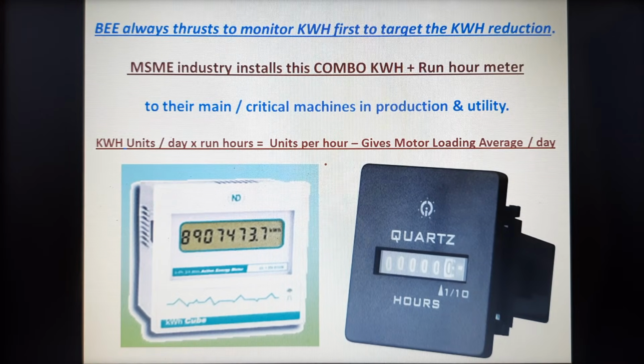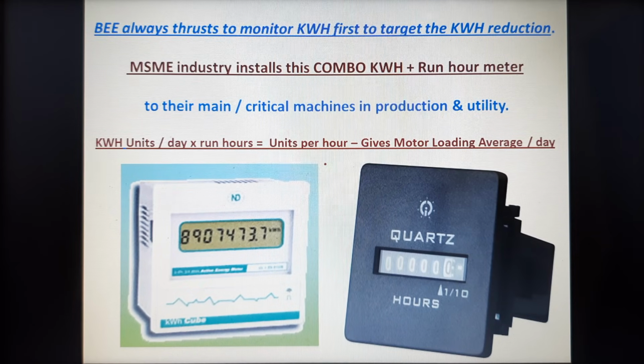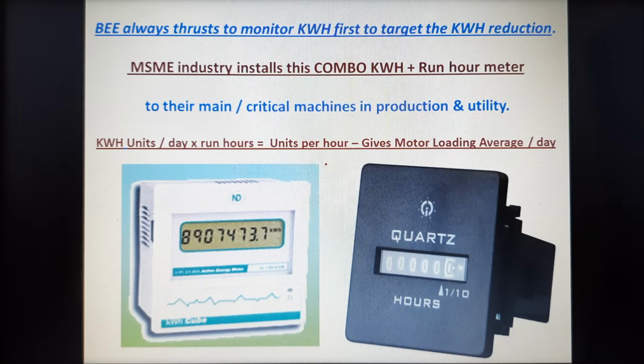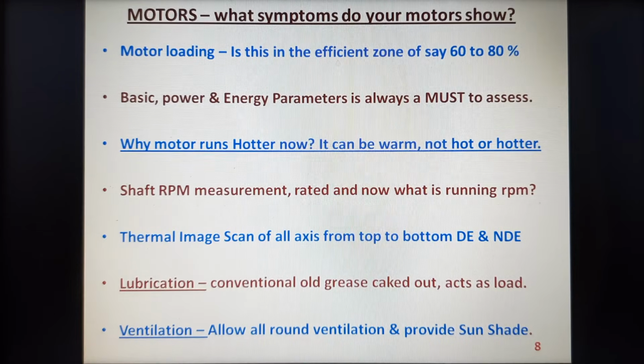This is what I am just talking about: combo meters of kWh and run hour meter to be installed on each and every pump, utility, compressor or blower, and on the production machines also. You know the kWh units consumed per day, and dividing by the run hours will definitely give the average units per hour consumed per day. You know the motor average loading. This will give an indication whether we are loading our motors correctly.